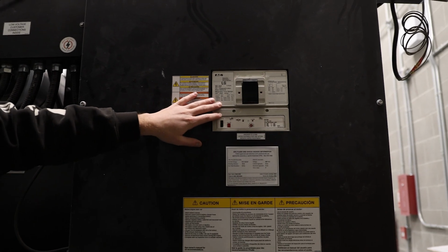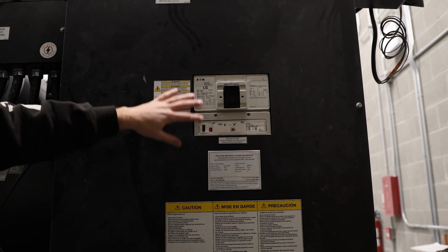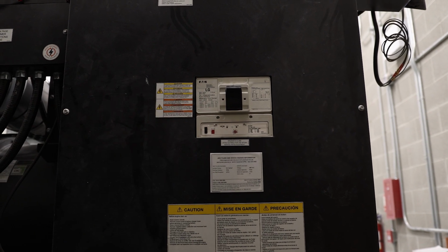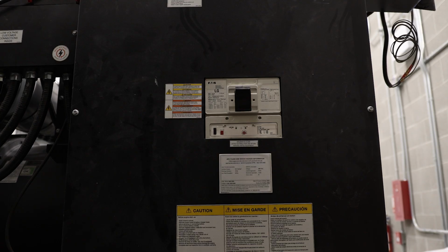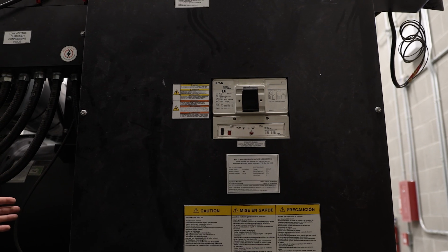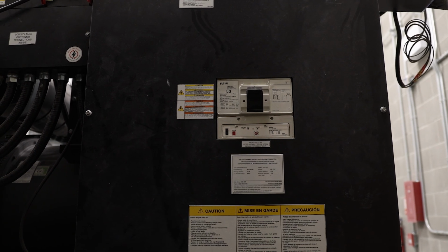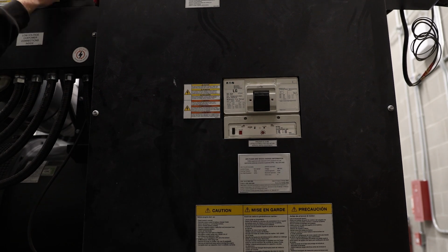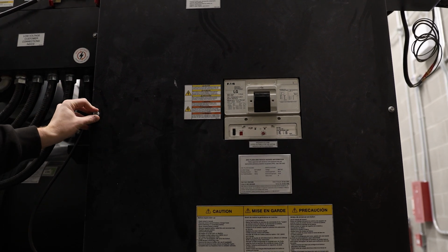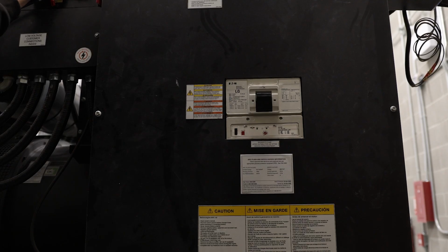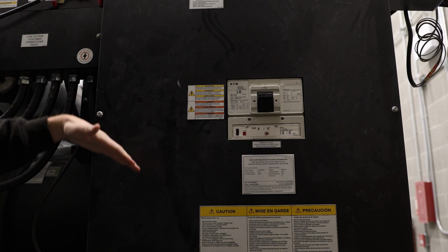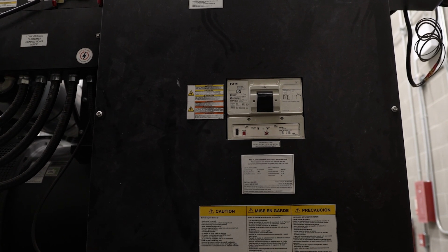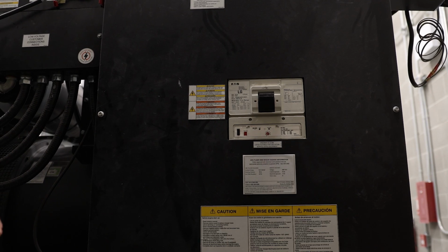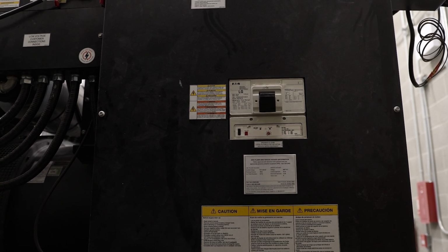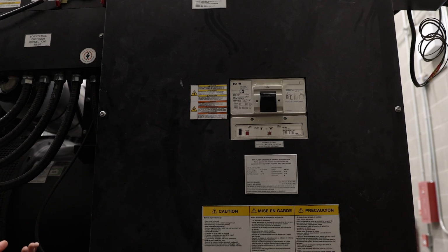This is our main control breaker out to our distribution panel, which is also in this room. This breaker is the lifeblood of the generator. It's feeding all the power the generator is making out to the building, well, out to the distribution. If the breaker were to trip or be left off, it's going to throw an alarm, and you'll have the alarm on the controller, main control breaker tripped. It'll do the same thing if someone leaves it off for whatever reason, but it needs to always be on, otherwise this thing will be running out here and it's not going to be powering anything.